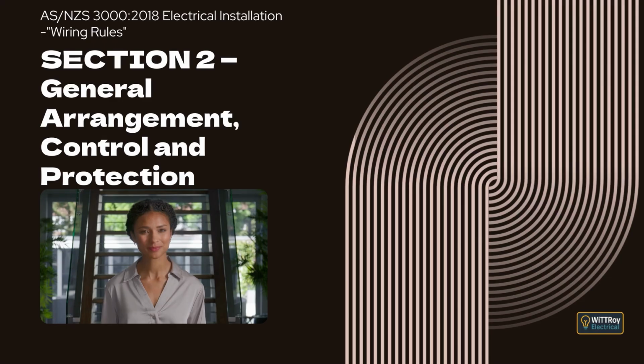It must not trick the user into thinking it is off when it is actually on. It must clearly show when the isolating contacts are open. The symbols O for off and I for on are considered acceptable ways to show this. The device must be installed so it cannot operate accidentally, even if hit or knocked. It must be able to disconnect all live conductors of the relevant supply and must be easy to reach.